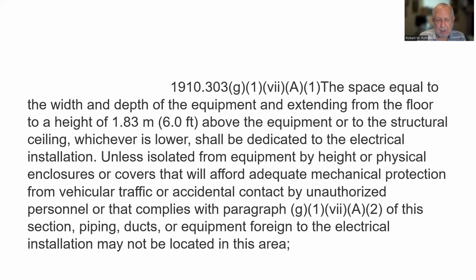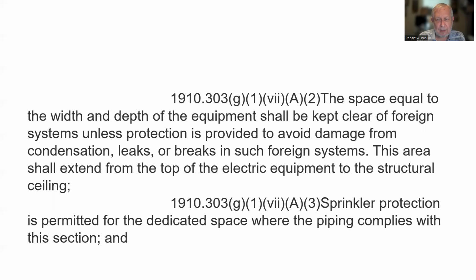This is just the height, 6 feet. And I'm not going to get into all the details on this. Okay, the space equal to the width and depth of the equipment shall be kept clear of foreign systems unless protection is provided to avoid damage from condensation, leaks, or breaks in such foreign systems. This area shall extend from the top of the electrical equipment to the structural ceiling.